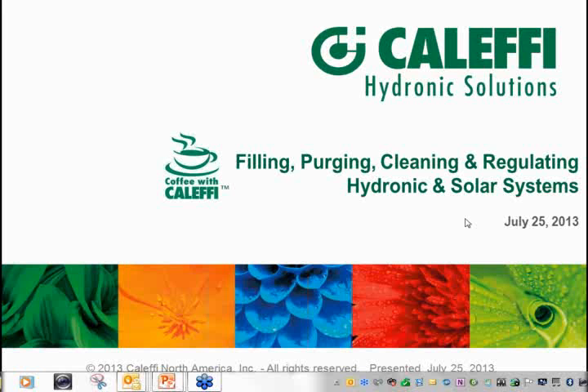Do they get 100% good purge right away? Probably not. It can take days for all the tiny little micro bubbles to work their way back to wherever you have a central air purge and come out. So depending on the equipment you're putting in and how much time and patience you have to purge it out when you're on the job with your fill system, that determines what kind of purging job you have in the end.